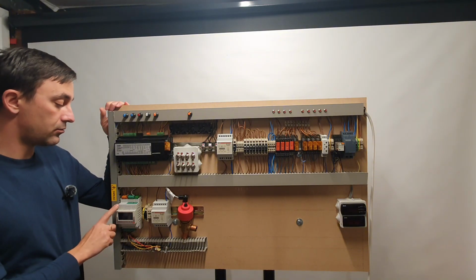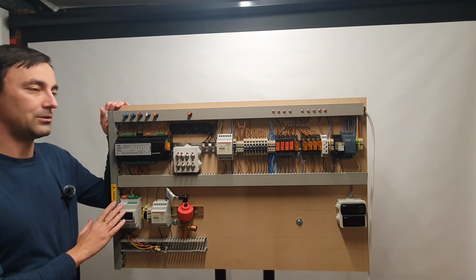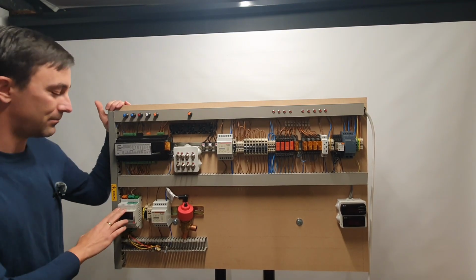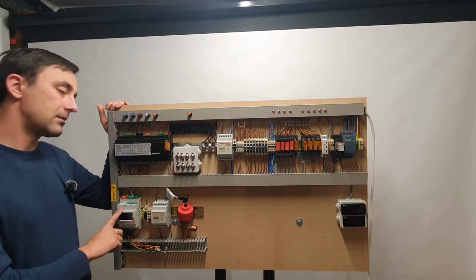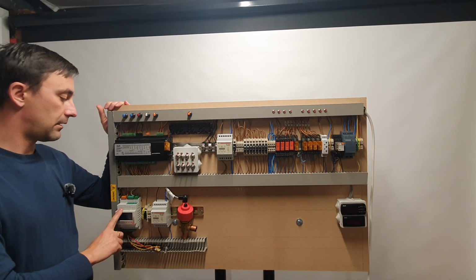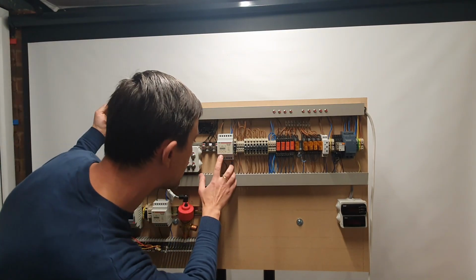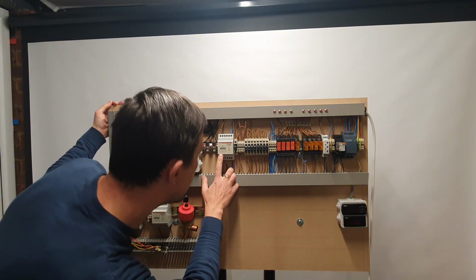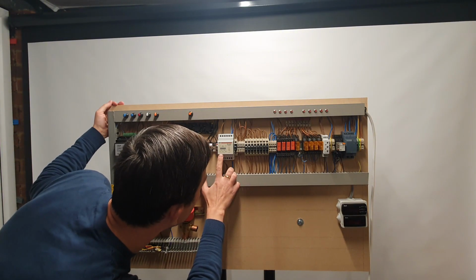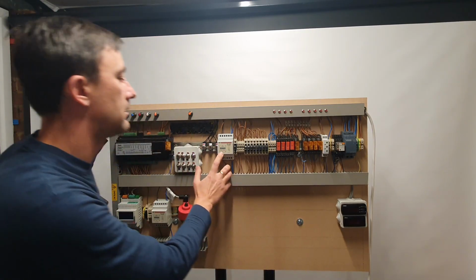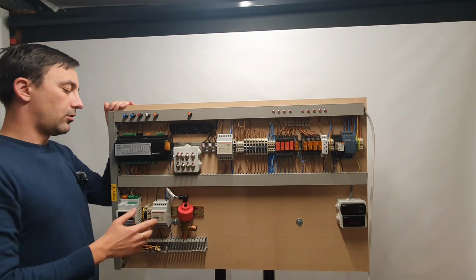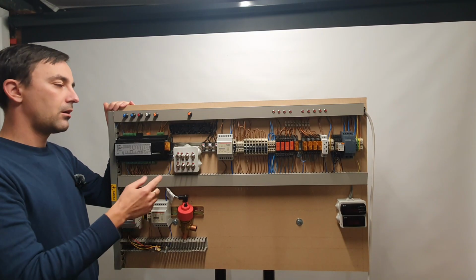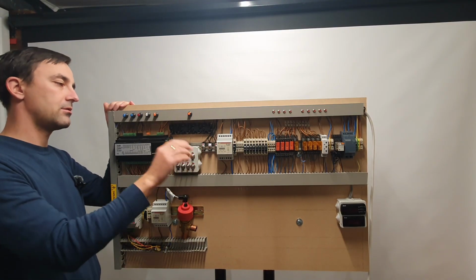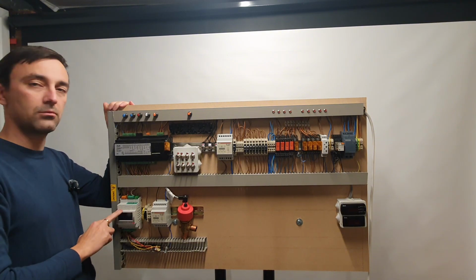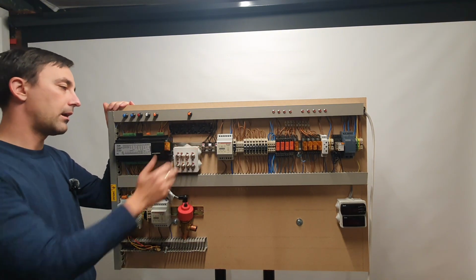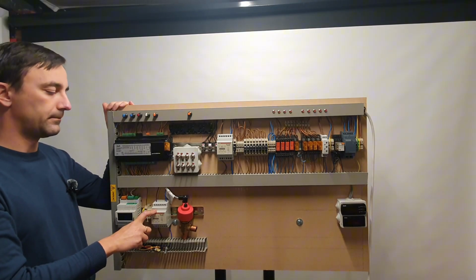It's because this controller, it does say in the manual, which is there for those who want to read all of it, and unfortunately it wasn't me when I first started. This controller can pull 2.4 amps, I think I'm right, it's 2.4 amps. But this transformer is rated at 1.3 amps, if I remember that correctly. Yes, around 1.3 amps. So I had to put a second transformer, wire it in parallel in order to increase the amperage, keep the same voltage, so I can run this one as well. So it was my mistake. So that's why now I have 2 transformers instead of 1.